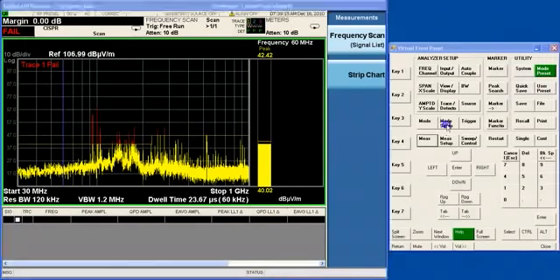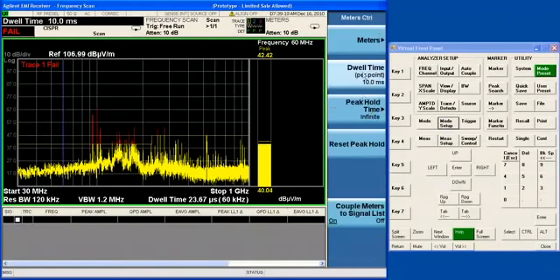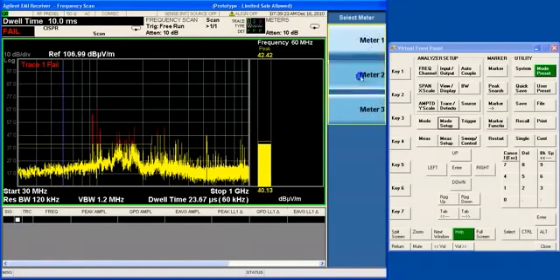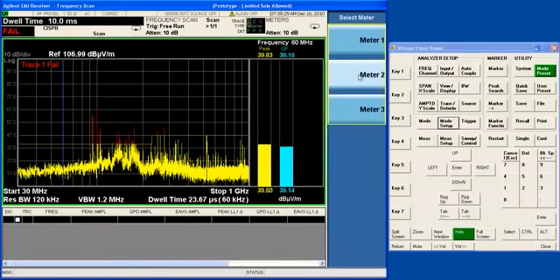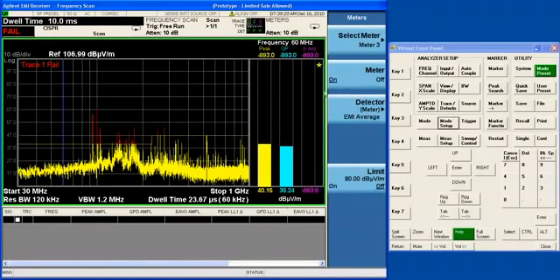I can turn on all three meters by going into mode setup and meters control. I can turn on meter two, which defaults to quasi-peak, and meter three, which defaults to the EMI average.